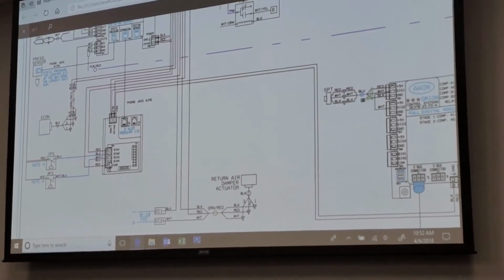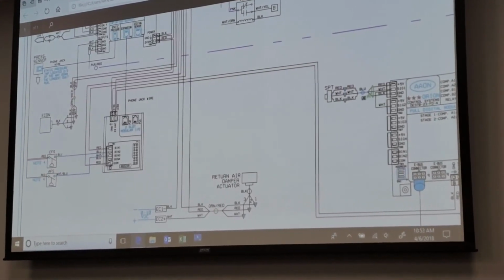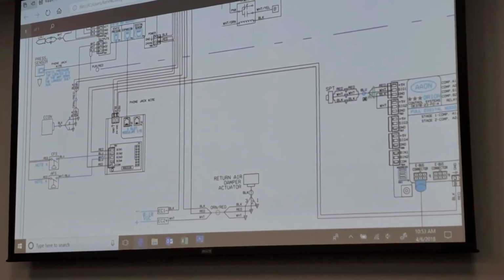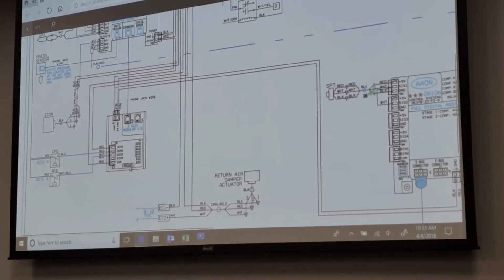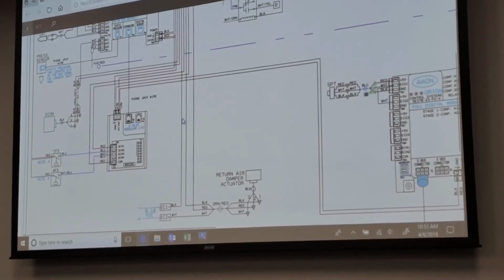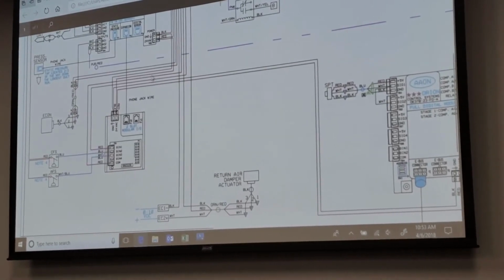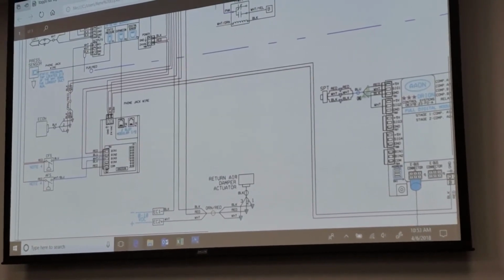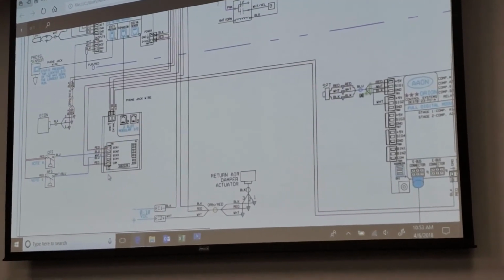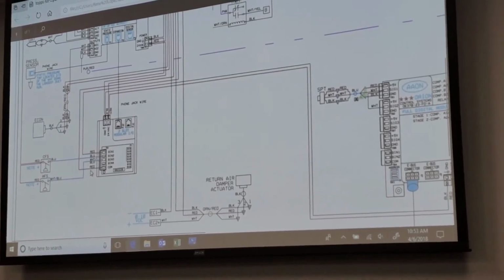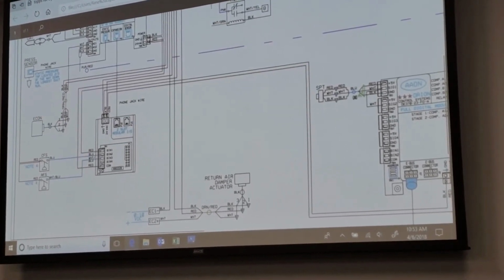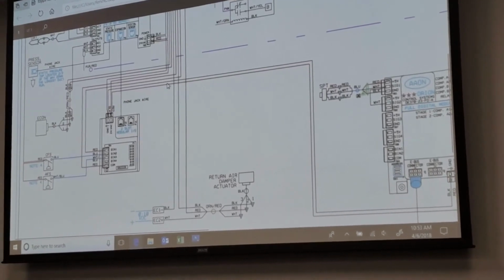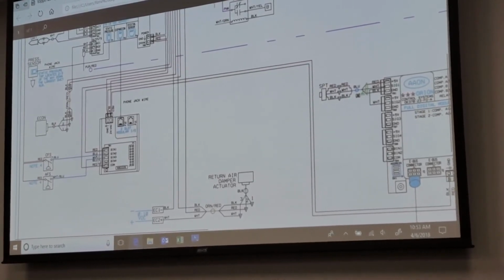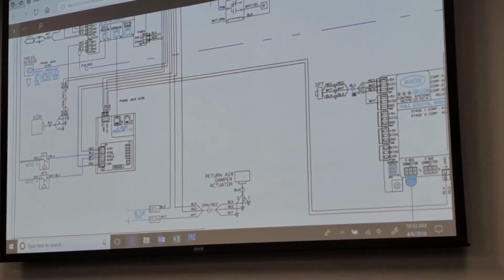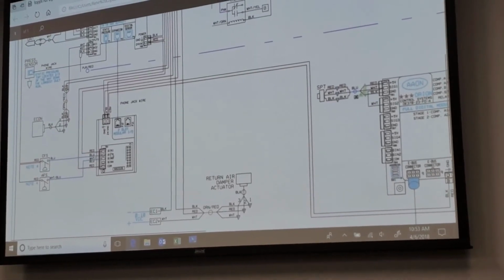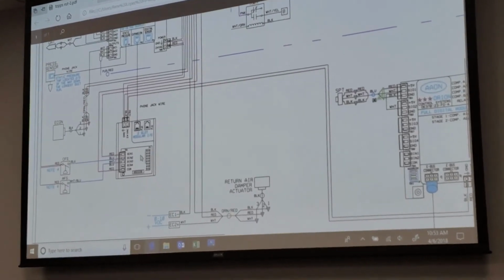Yeah, we got a warranty board. How many boards blew up? That one was only one board. We caught it real quick. When we did start up, it was actually one of my other guys who started it up. I went over there and started looking at it, and I went, "Well, damn, that comm shouldn't be a red wire. That should be a black wire. That's just a common." So I went back, and yep, that's wrong. Called the factory, said, "Hey guys, look at this." They went, "Yep, it's wrong. We'll send you the board." Wiring diagram needs to be changed on that.